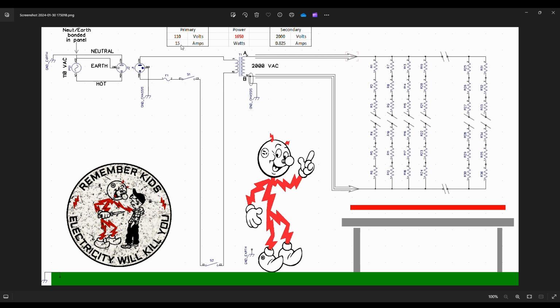That means we're going to be pulling 15 amps on our input side. Now if you don't have a fuse here, a circuit breaker of some sort, you can allow far more than the 0.825 amps to flow through the block of wood.